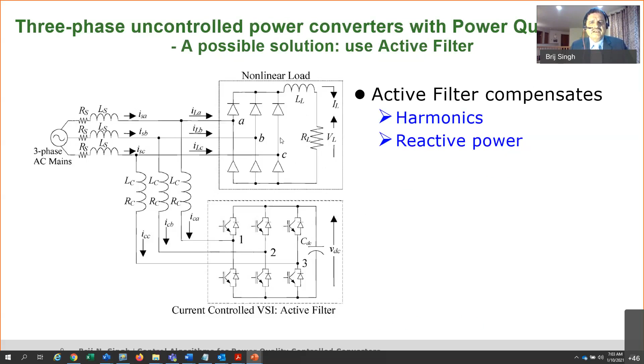So what is the active filter's job? It compensates harmonics and it compensates reactive power. Any load where the voltage waveform is not sinusoidal usually has reactive power at the PCC, so there's total demand distortion, total harmonic distortion. If current and voltage are not in phase because of distortion in the current waveform, then it has some reactive power, so the active filter also supplies reactive power.